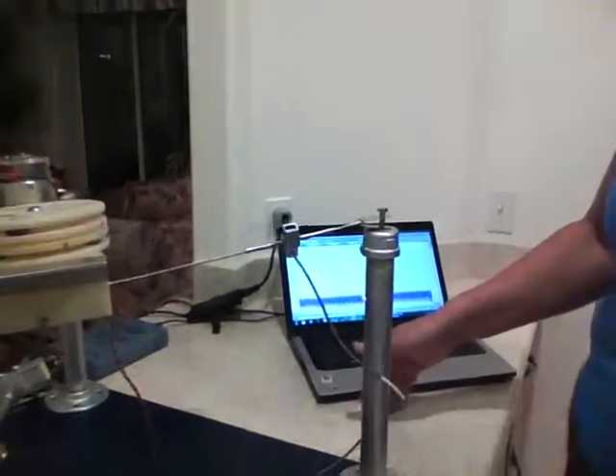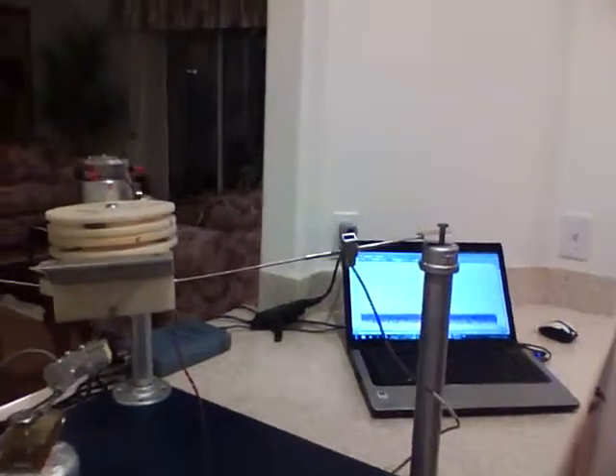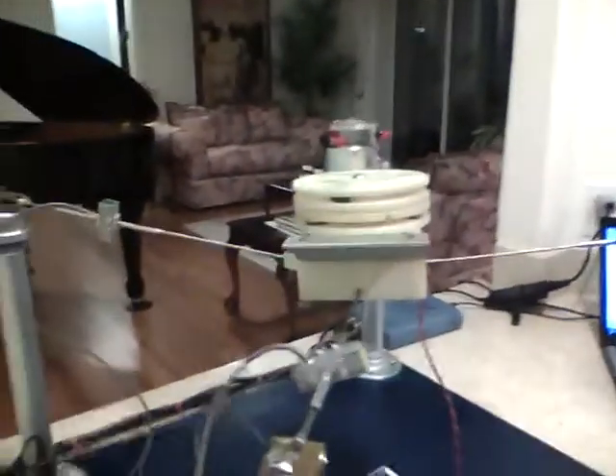So then you read them out over on the screen? That's correct, and I set all of them up for 1.3 volts as a center voltage. So now we're all basically zeroed out — all the gains were set for exactly the same gain. So are we ready to run no-load test number two? No-load test two, get some more data.